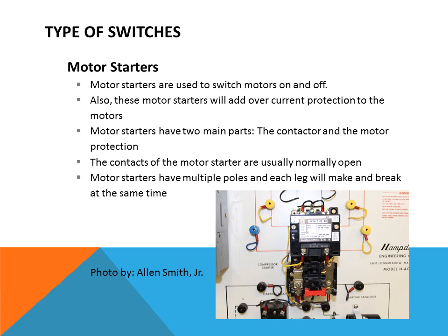But the difference from a contactor is that motor starters are designed to handle the current flow for larger types of motors. The motor starter also has a motor protection portion, which will sense the current flow through each leg, and if the current is higher or unsafe through either of the legs, it will open up the control circuit to disengage the motor.